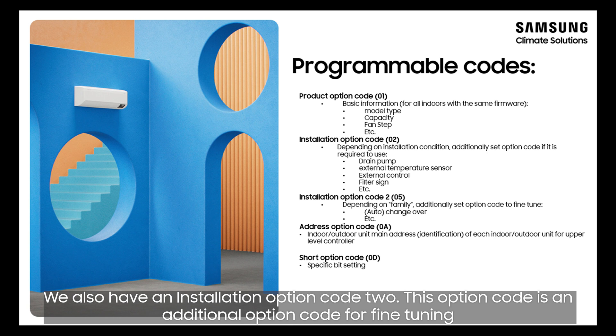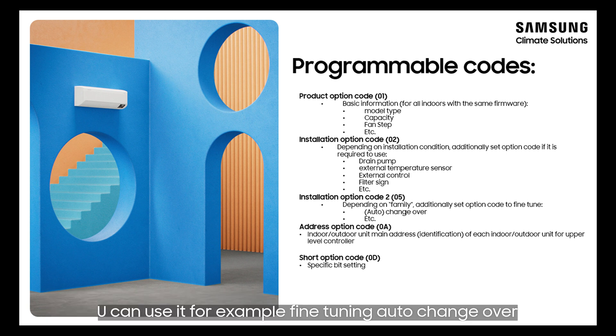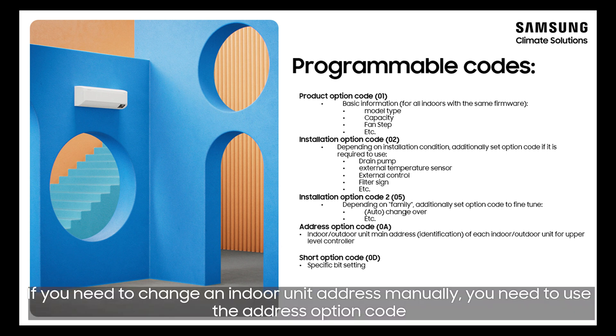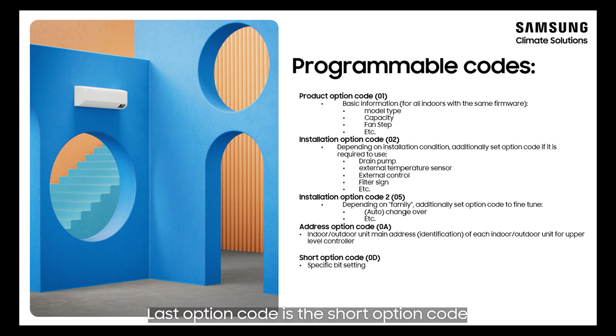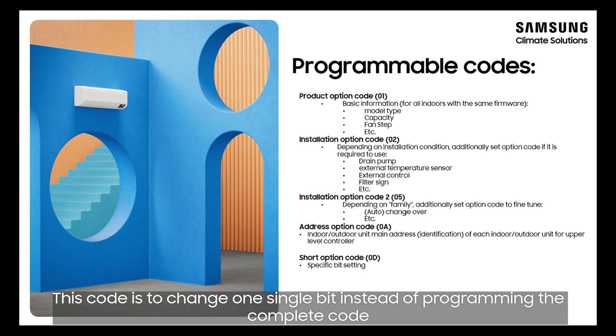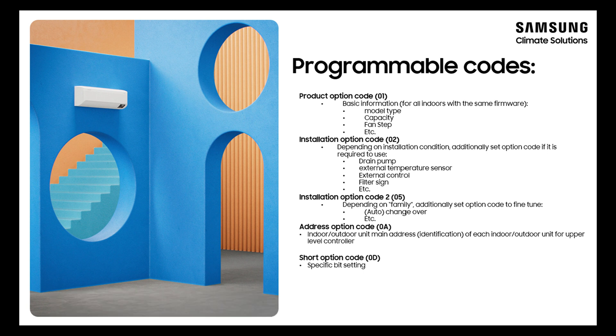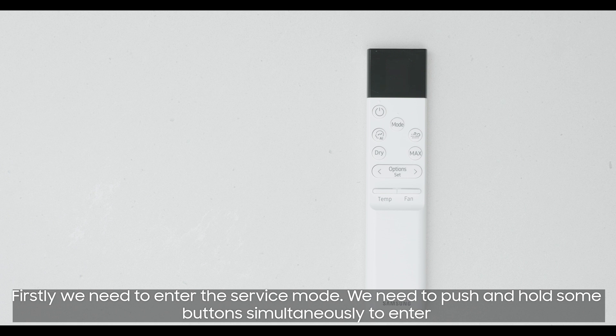We also have an installation option code 2. This option code is an additional option code for fine tuning — you can use it, for example, for fine tuning auto changeover. If you need to change an indoor unit address manually, you need to use the address option code. You can change indoor and outdoor unit address for upper level controller. The last option code is the short option code — this code is used to change one single bit instead of programming the complete code.